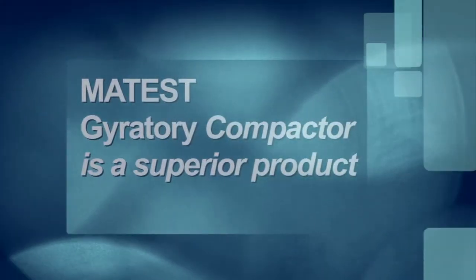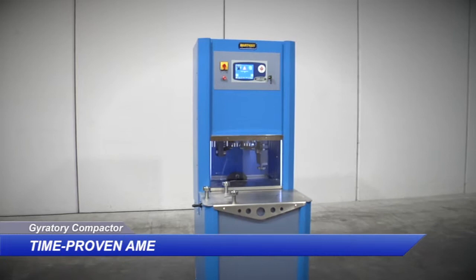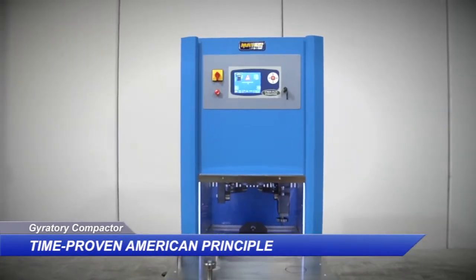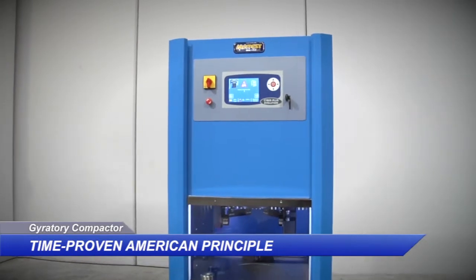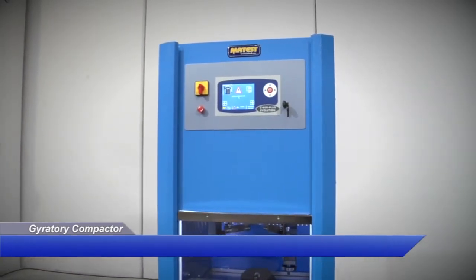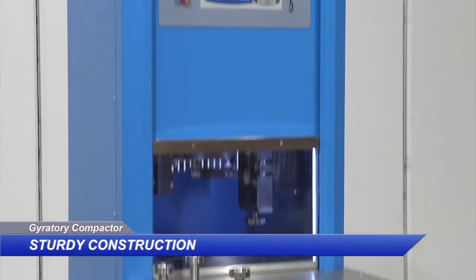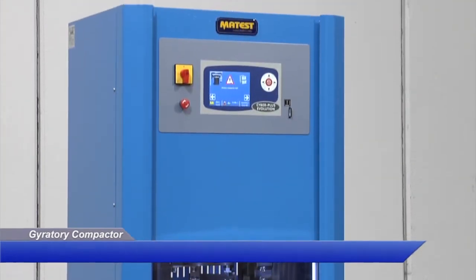The Matest Gyratory Compactor is a superior product, developed following the time-proven principle used on the original Texas DOT gyratory compactor. The principle is dependable, easy to validate, and widely understood. Its highly sturdy construction ensures the gyratory angle is maintained under all load conditions.